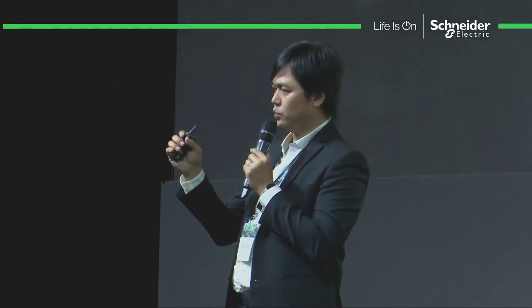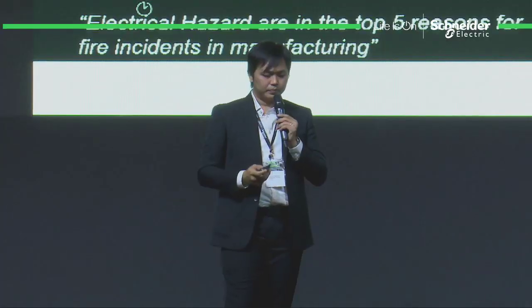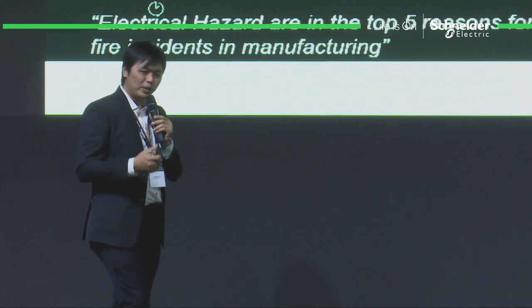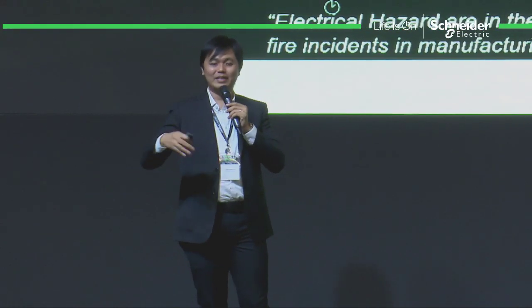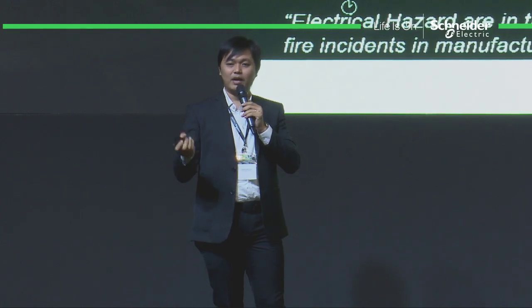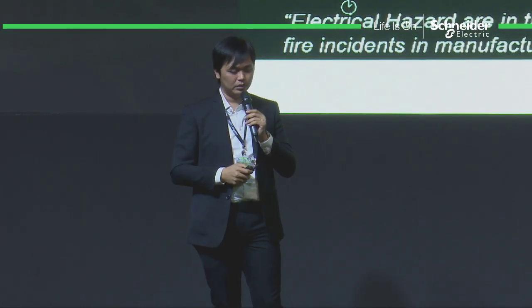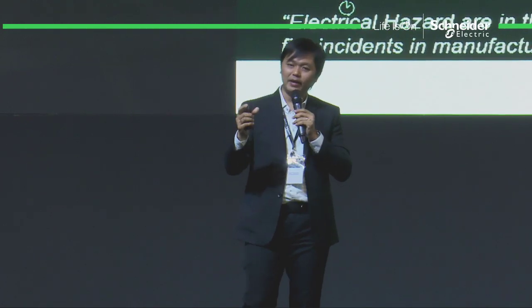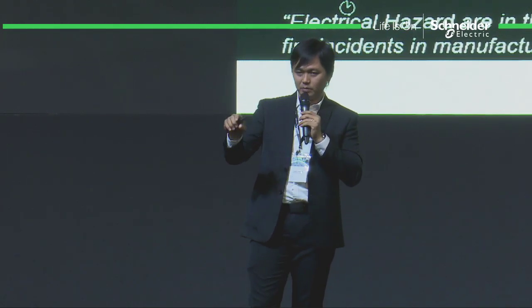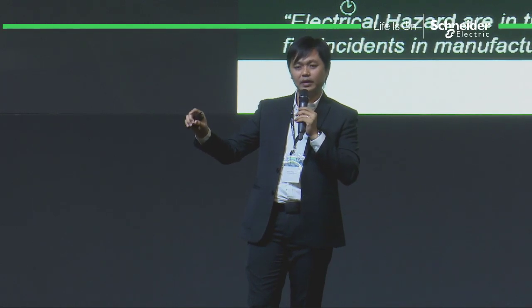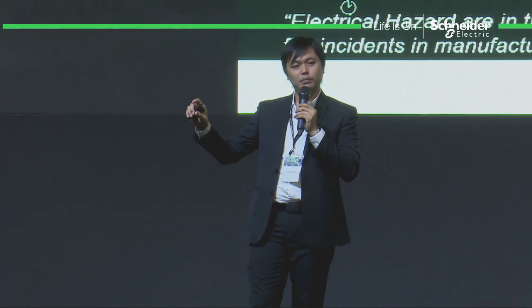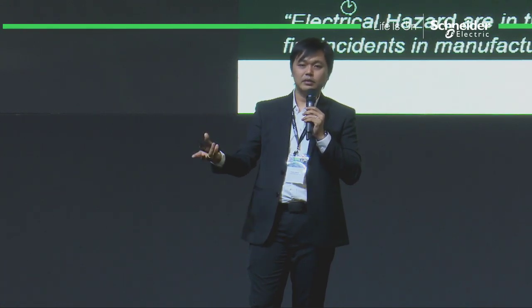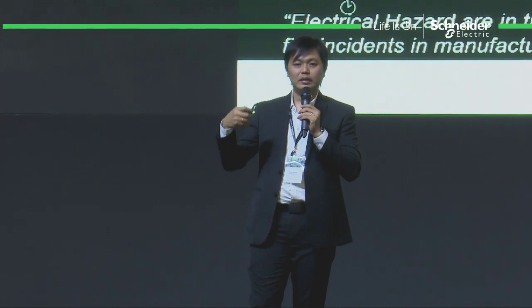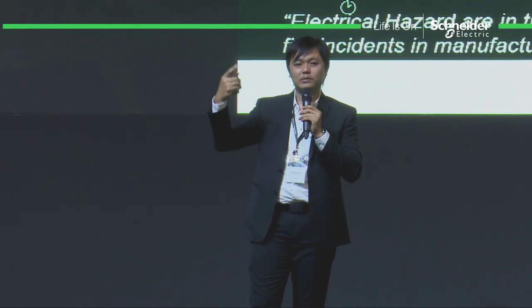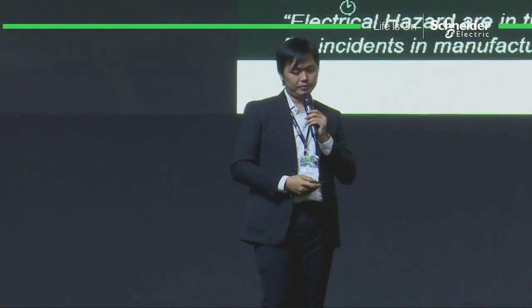These machines are impacted by very small power quality disturbances, like dips, sags, and swells, and can shut down or restart when this kind of poor quality disturbance occurs. So we have the solution to pinpoint where the problems come from, which machine creates the poor quality issue, which motor creates a dip, for instance, which motor has broken windings that leads to voltage dip.